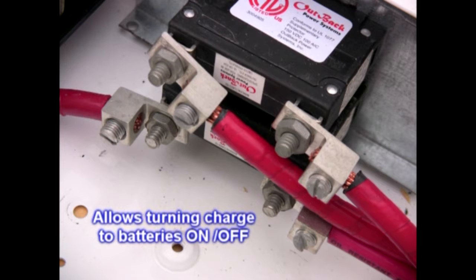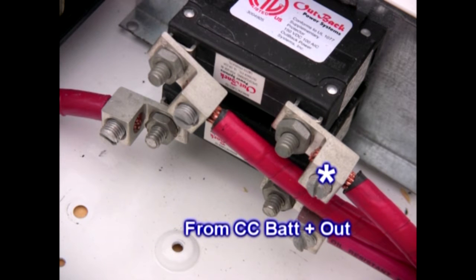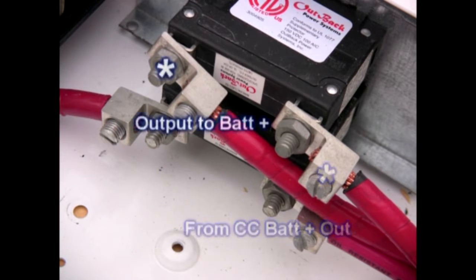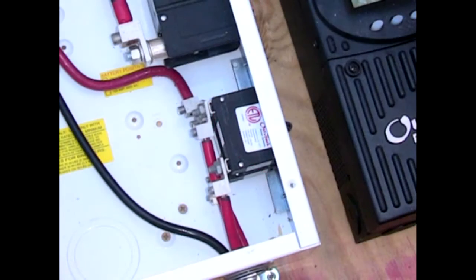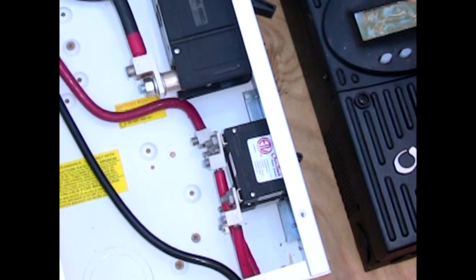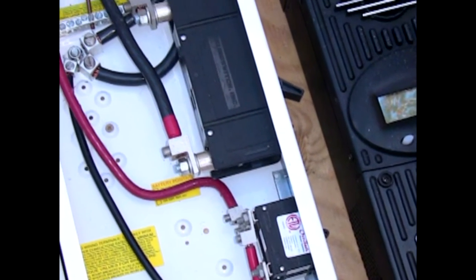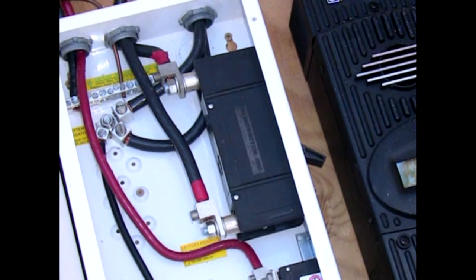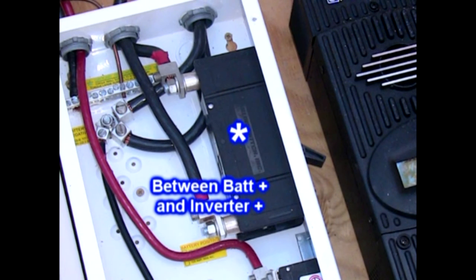So the output of the charge controller goes through the small breaker and then comes back out the bottom of the strain relief and goes over to the batteries, and that completes the circuit of the output of the charge controller to the batteries. Now let's look at our big 175 amp breaker, and this is for the output of the power of the batteries going to our large inverter.